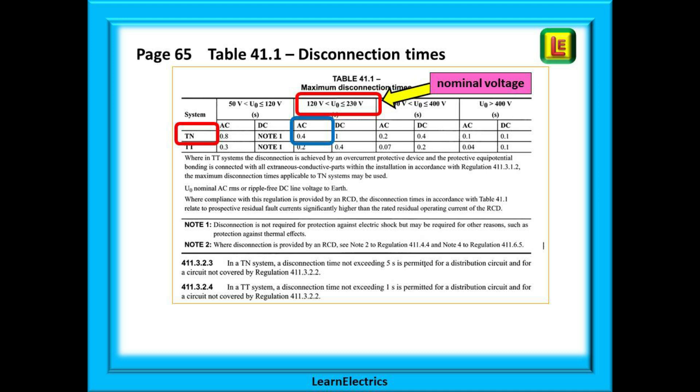Let's assume that our circuit is a final circuit and it is below the amp limits specified. Table 41.1 on page 65 will tell us the maximum disconnection time for safety for different nominal voltages and different earthing systems. Nominal voltage is what we call the voltage, not what we actually measure. This means that in a household kitchen we call the nominal voltage 230 volts and that is what we use for all of our calculations even if we measure 240 volts or 250 volts.